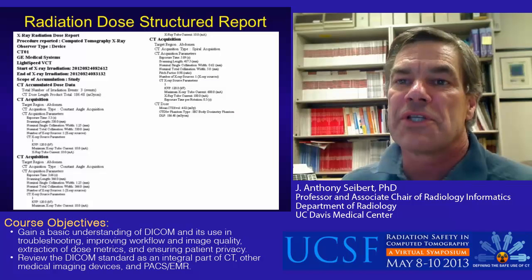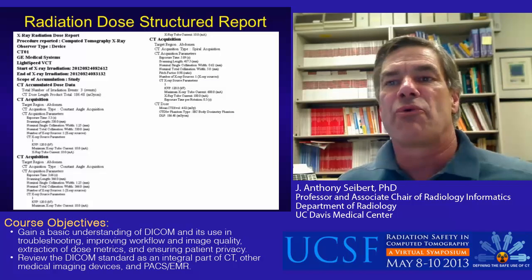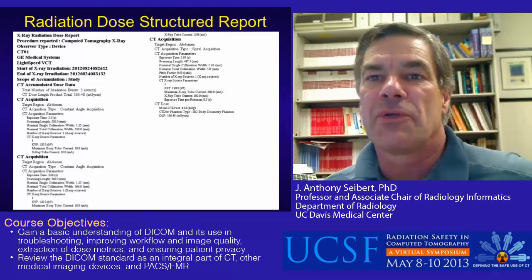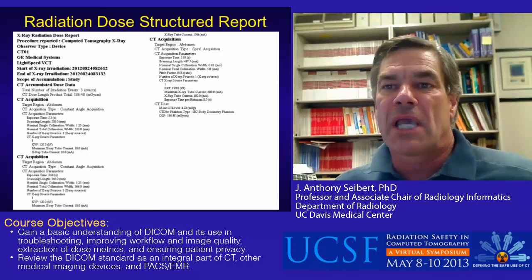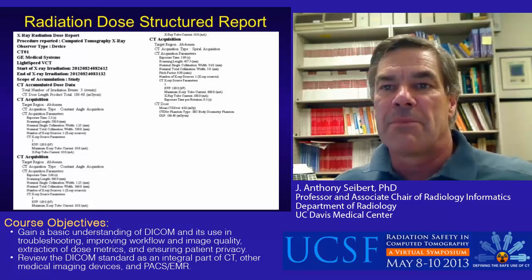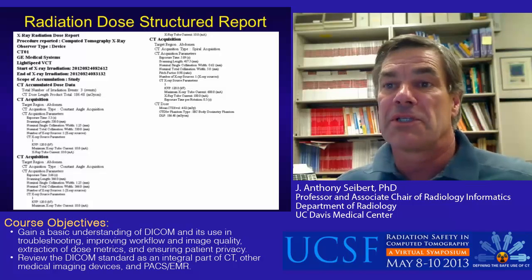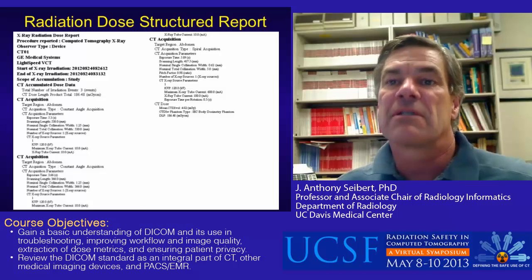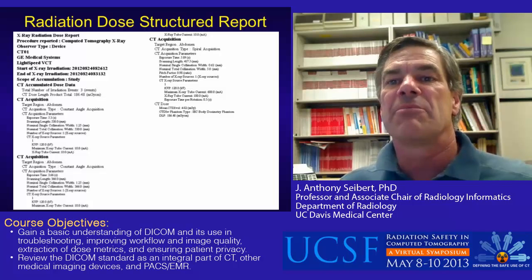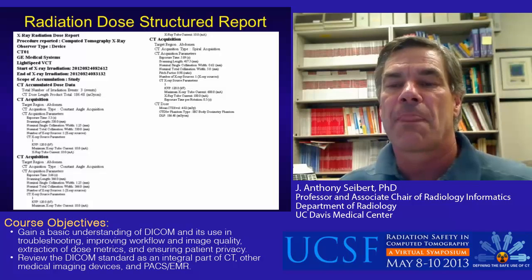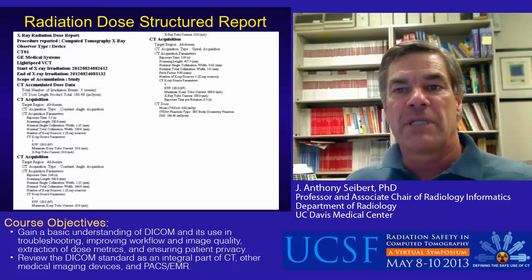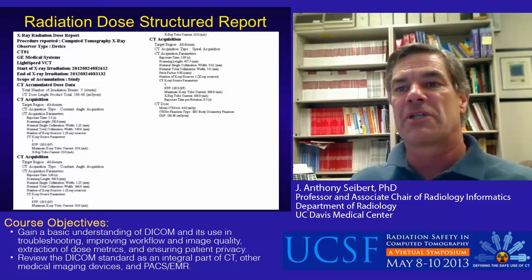Shown in this example is the Radiation Dose Structured Report by a manufacturer. Listed are each of the radiation events, including the localizers and the actually scanned image, with pertinent details such as region scanned, type of acquisition — spiral helical in this example for the third acquisition event — acquisition parameters with CTDI-VOL, DLP, and the phantom used for CTDI calibration. The RDSR simplifies the efforts of accurate and complete dose information extraction in CT.